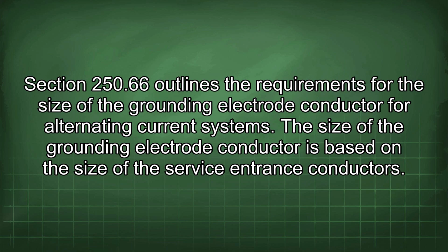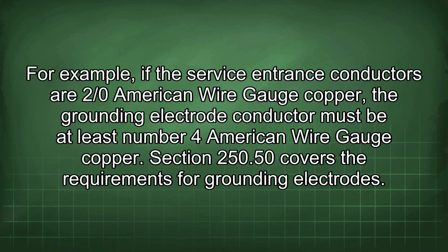Section 250.66 outlines the requirements for the size of the grounding electrode conductor for alternating current systems. The size of the grounding electrode conductor is based on the size of the service entrance conductors. For example, if the service entrance conductors are 2/0 American wire gauge copper, the grounding electrode conductor must be at least number 4 American wire gauge copper.